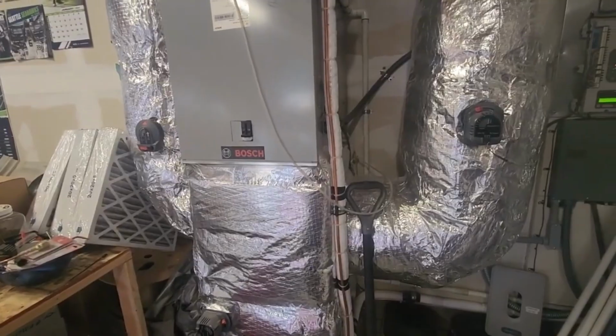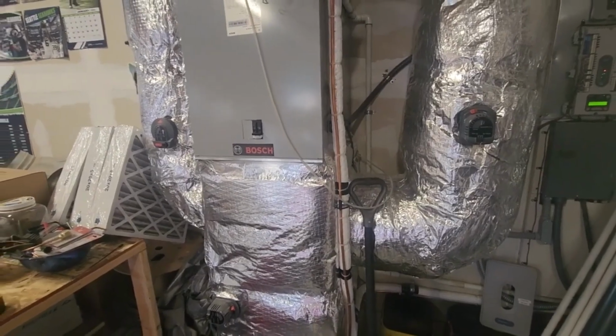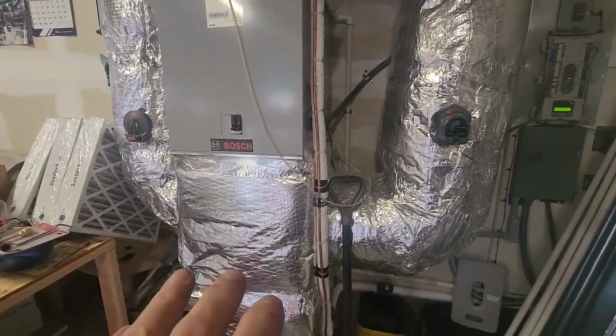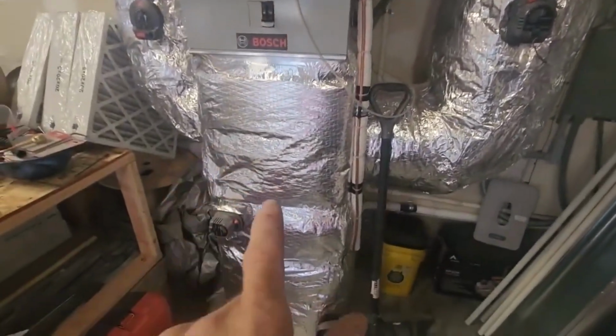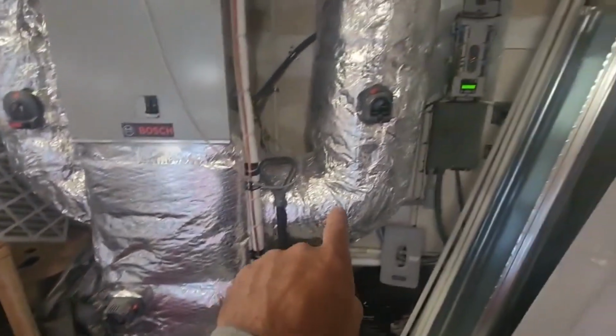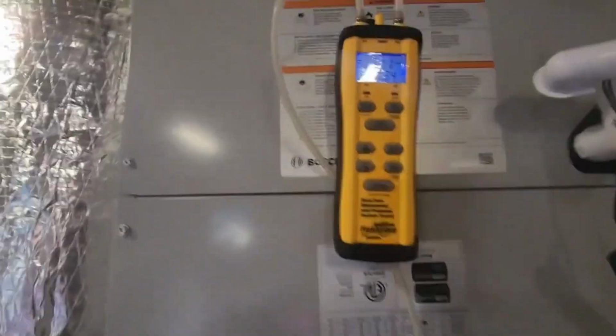Okay guys, this is the beauty of the Bosch system, the beauty of 2-stage equipment altogether, coupled with that zone panel. I have the downstairs damper shut. The only one that's open is this one. And look at my static.